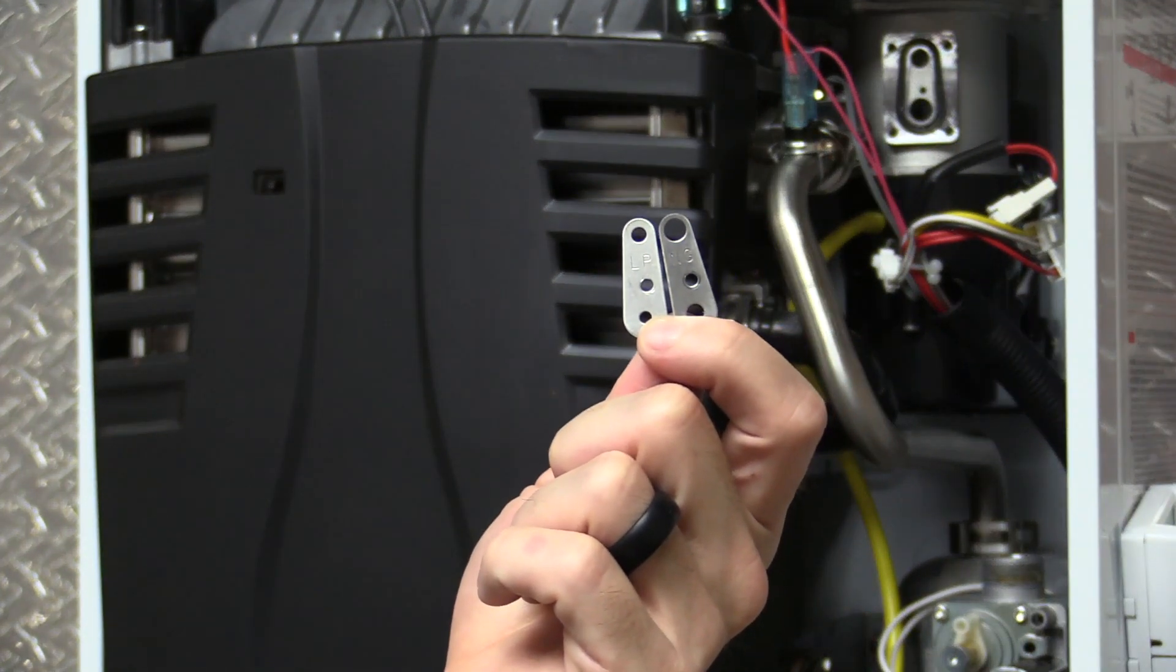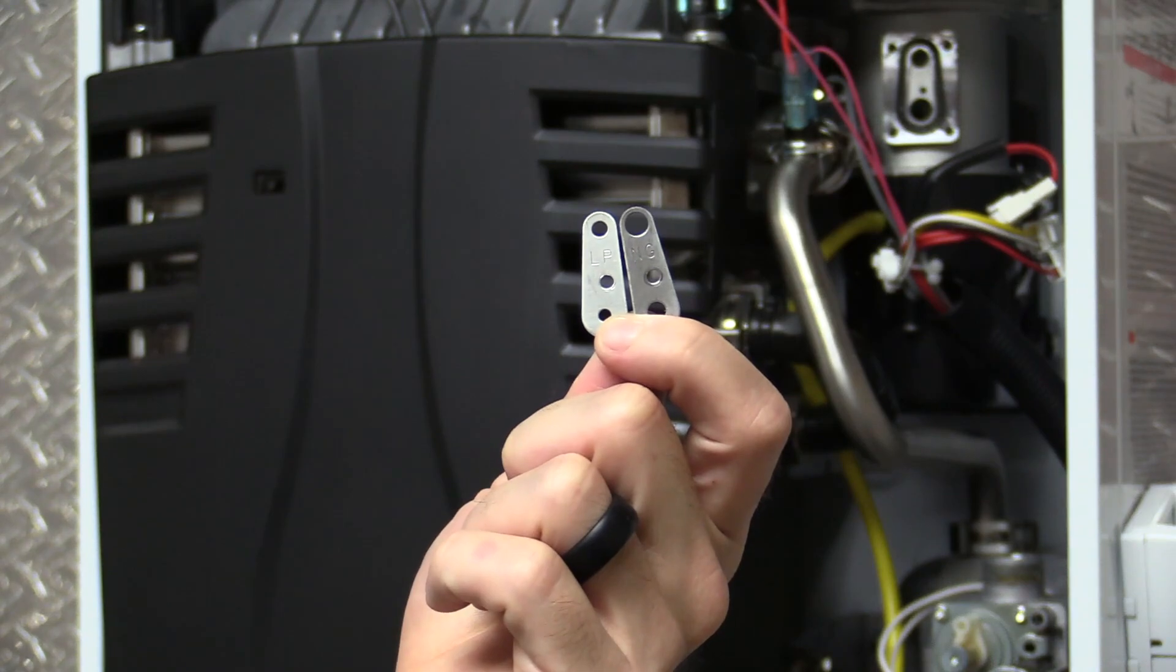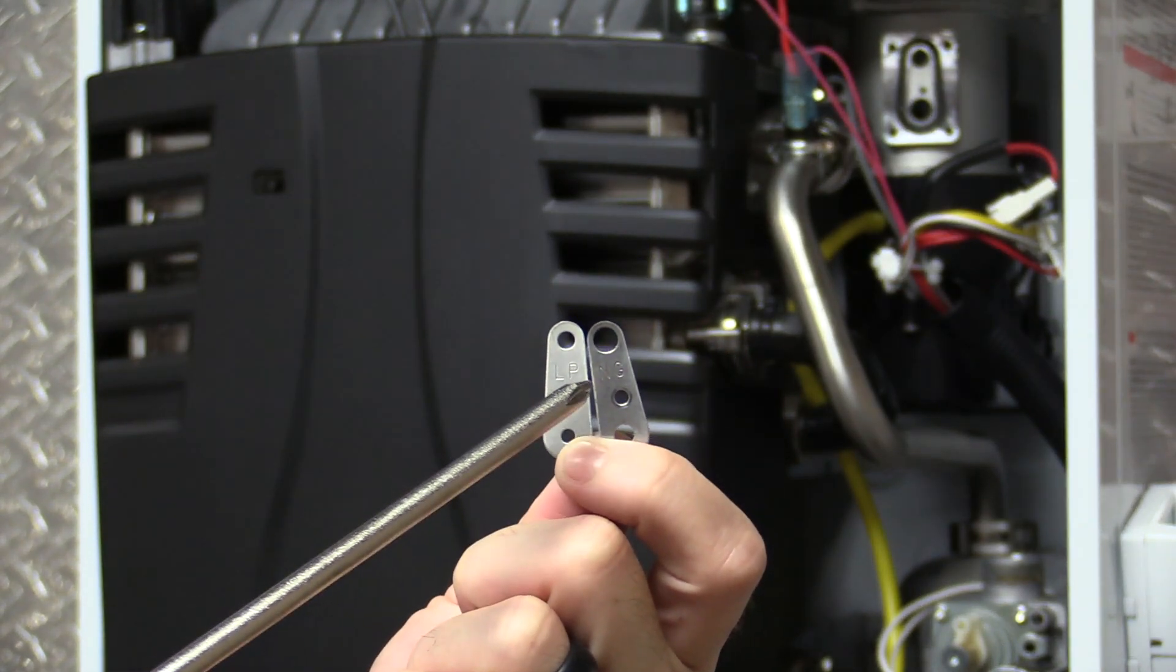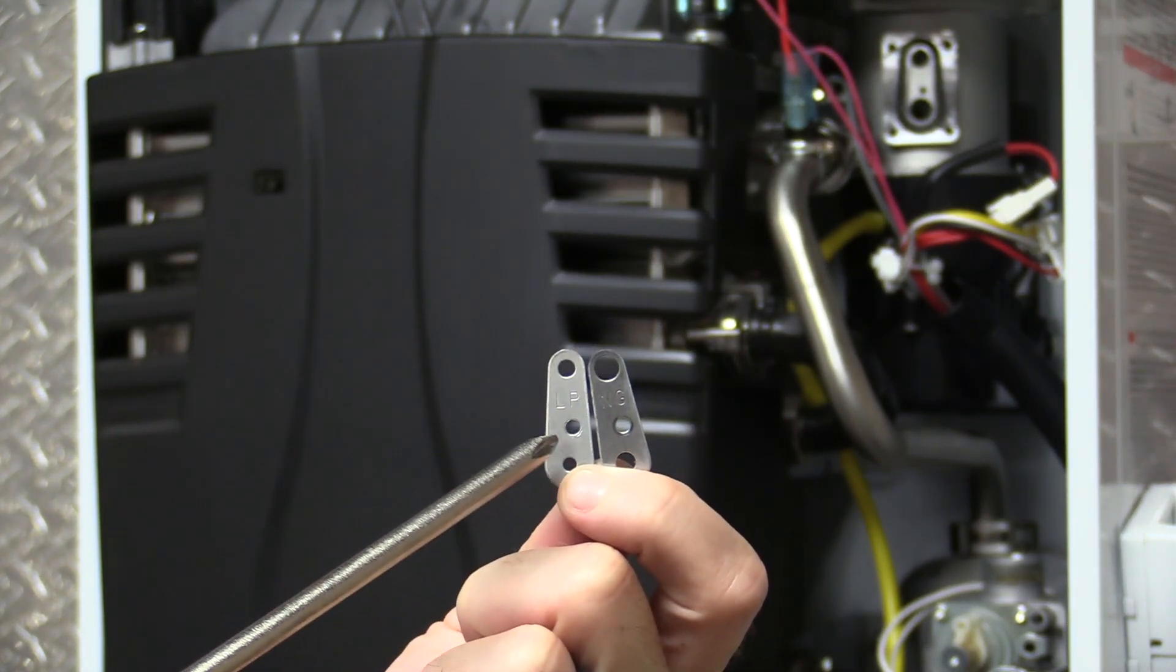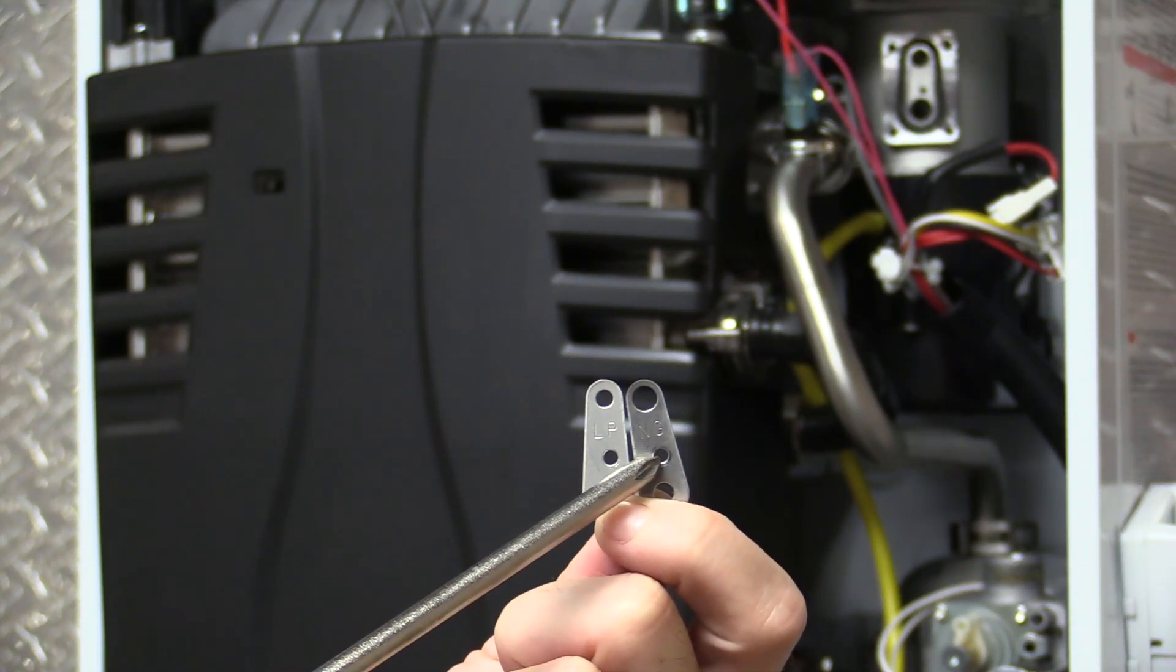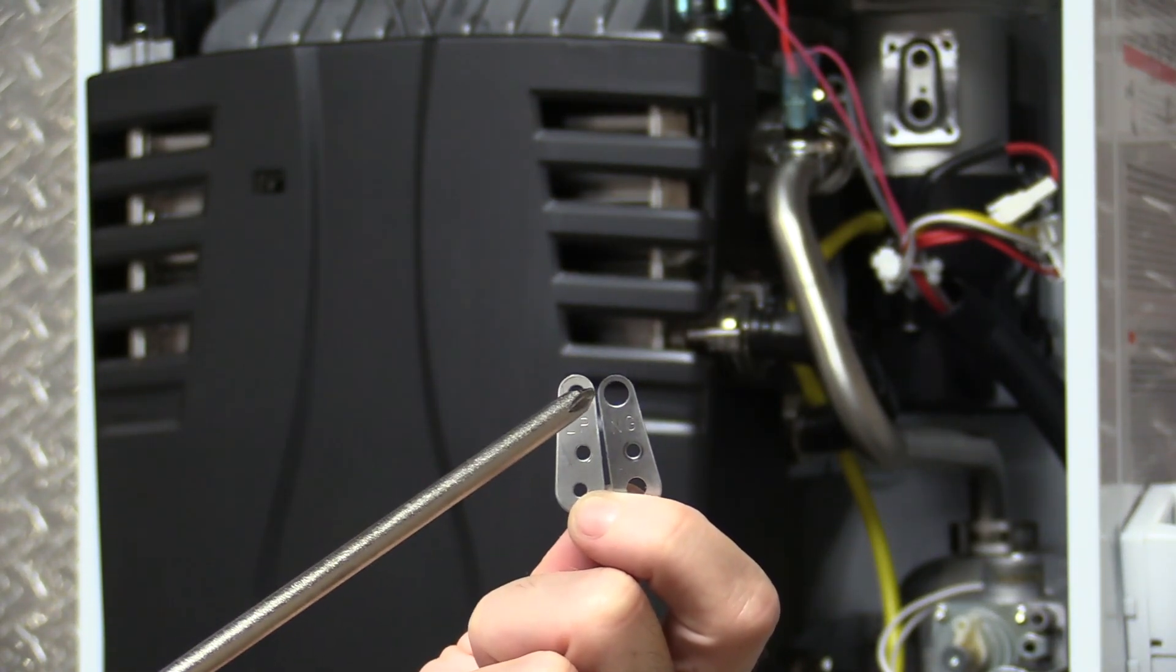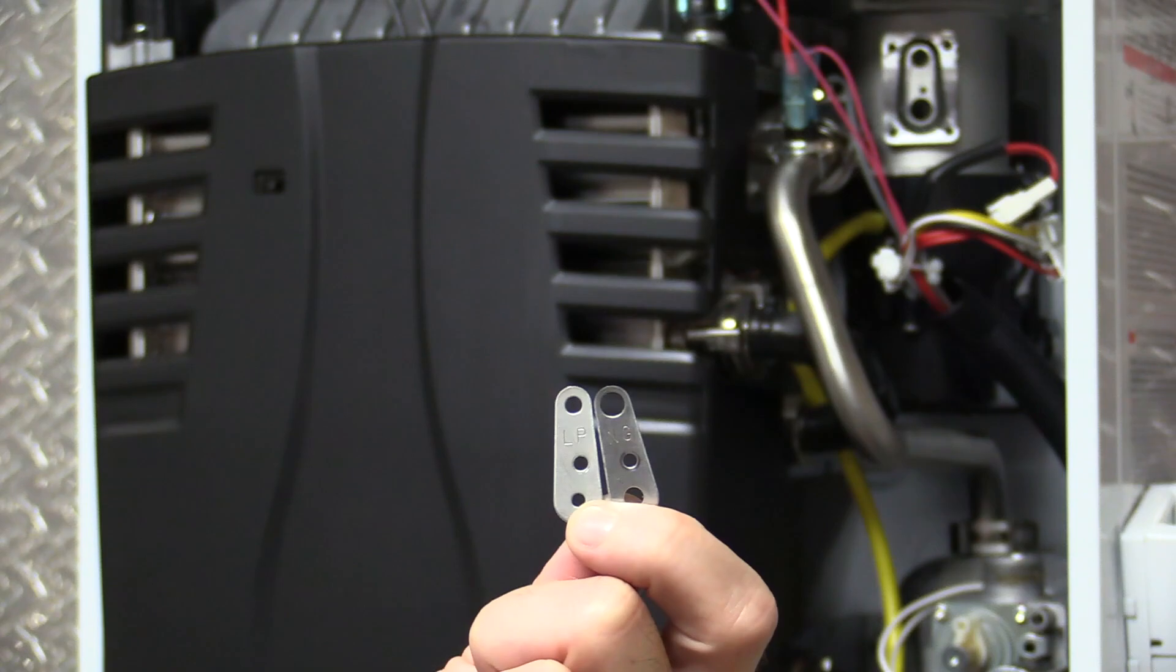So here you can see the natural gas and the LP orifice plate. They're stamped with the type of gas that they are set for. This here is your set screw hole, and then you can see that the LP has smaller holes.